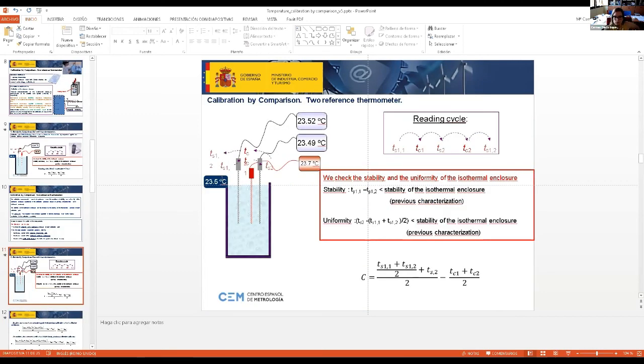So with two reference thermometers, and with our thermometer under calibration, this is the reading cycle. First reading of our first standard, first reading of the thermometer under calibration, first reading of the second standard, second reading of our thermometer under calibration, second reading of the second standard, and second measurement of our first standard. With these measurements, we can check the stability of the isothermal enclosure, I mean the evolution of the temperature with time of this liquid, and also the uniformity. Once these values are lower than the values obtained in the previous characterization of our isothermal enclosure, we are at the appropriate time to perform the measurements and to determine the correction of the thermometer under calibration.